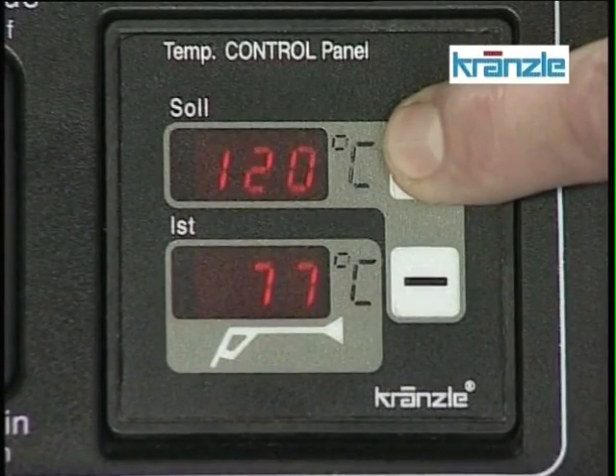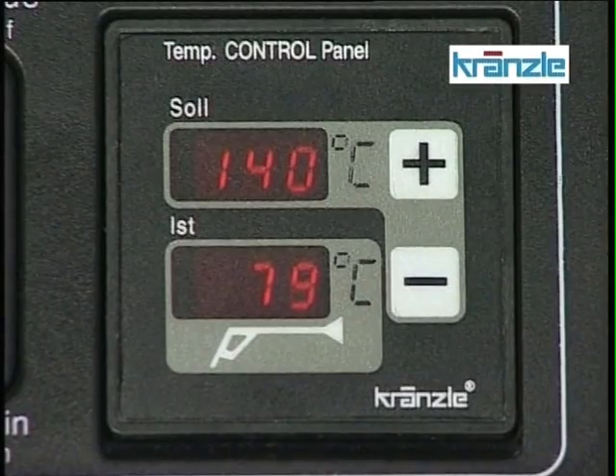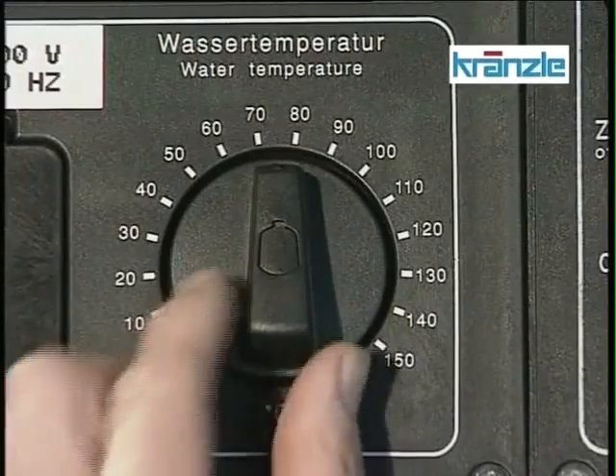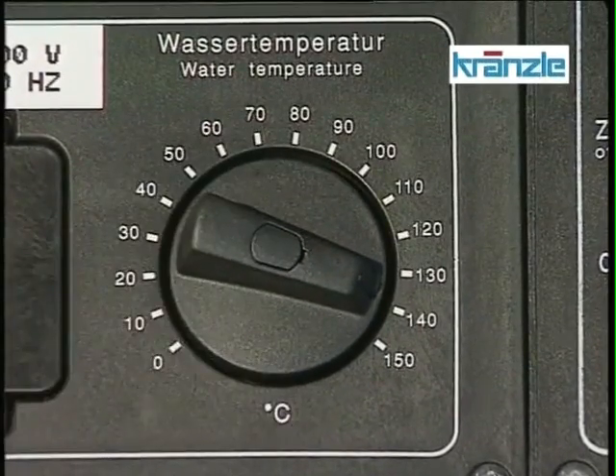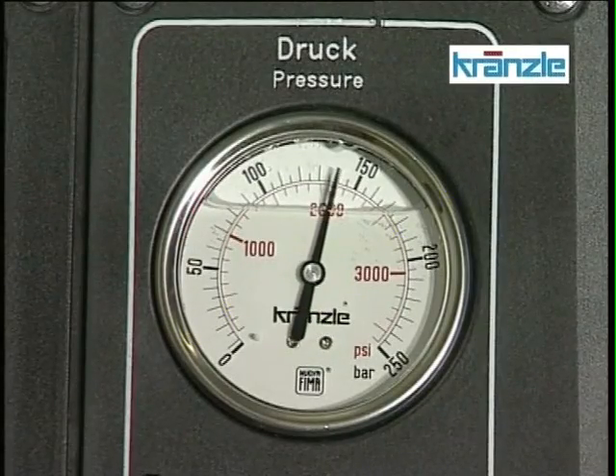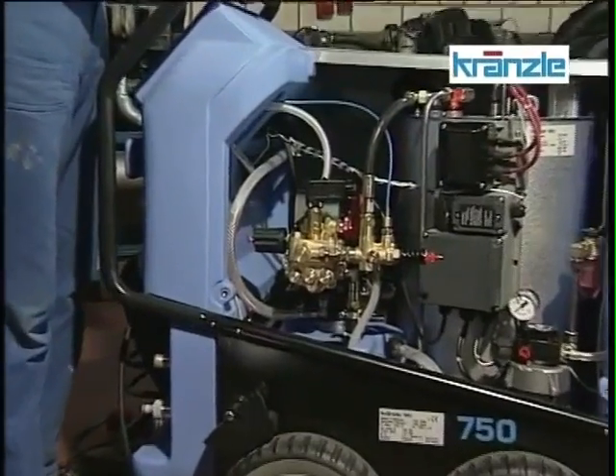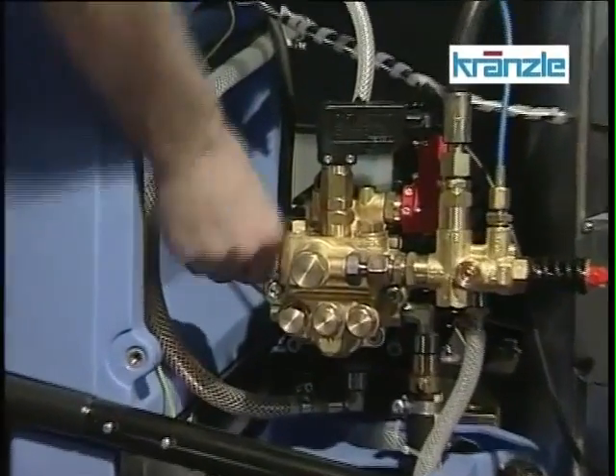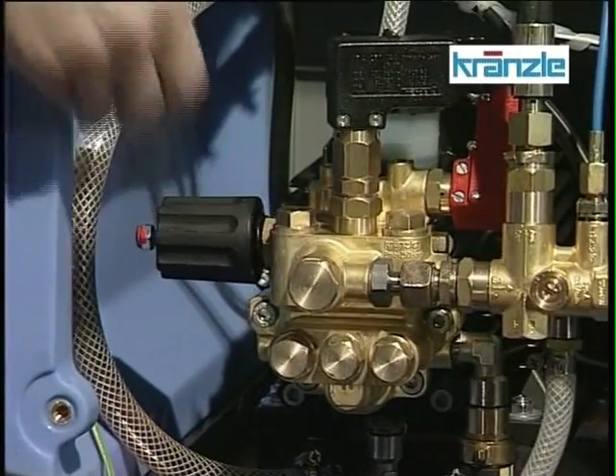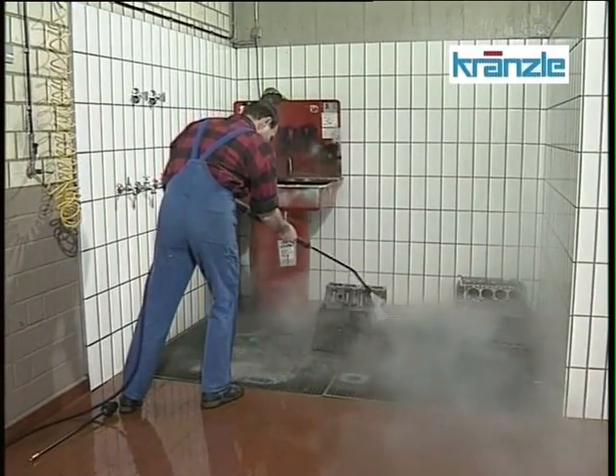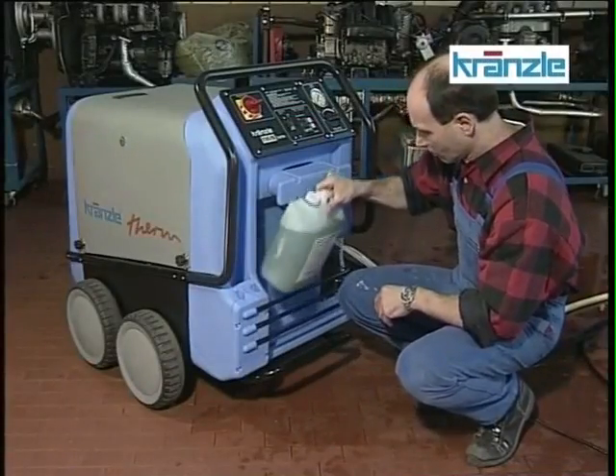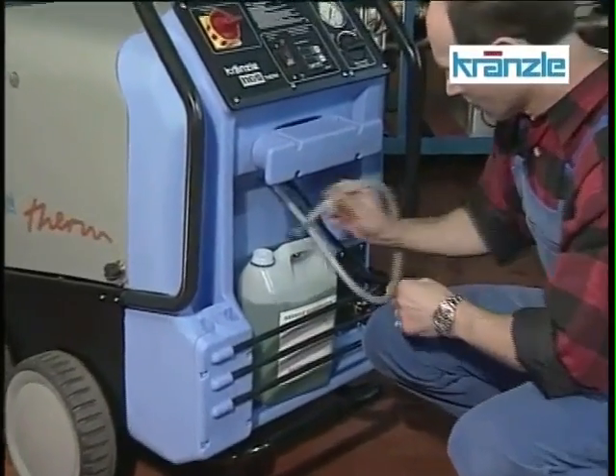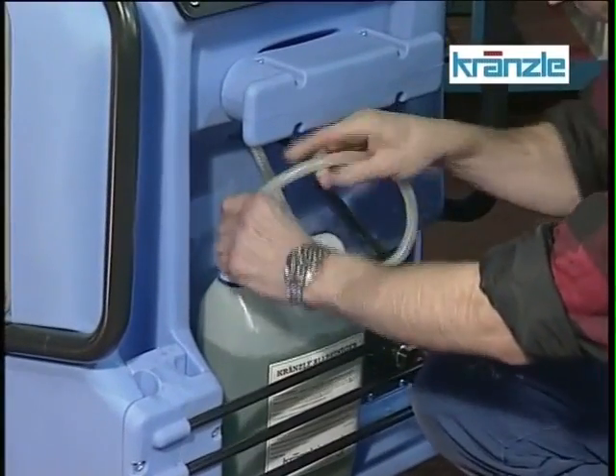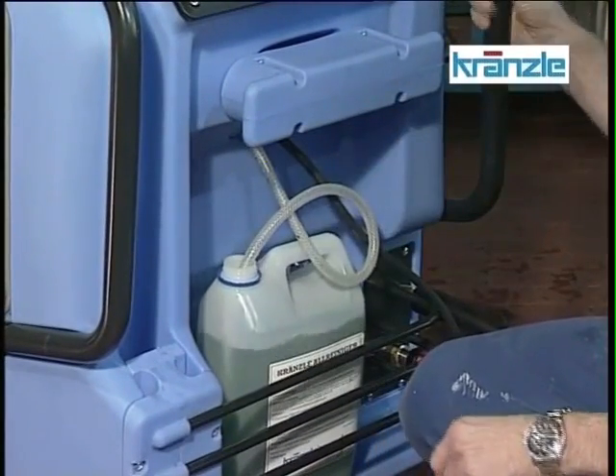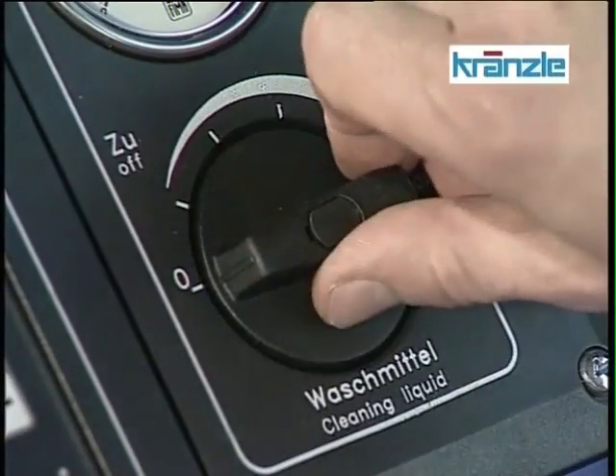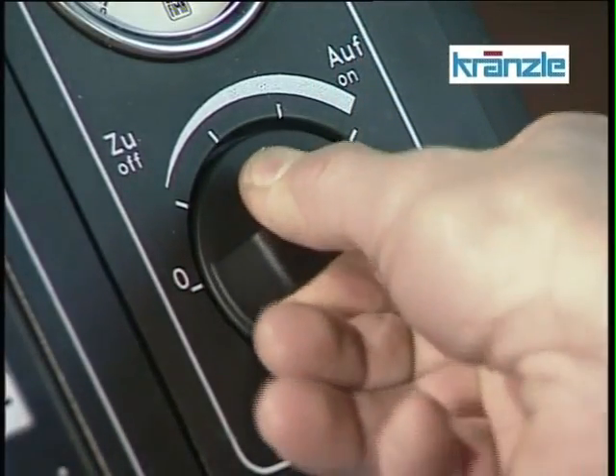This is how to activate the steam stage up to 150 degrees Celsius, and again at this knob on the 0 series. On all models, the working pressure and the steam stage are set on this hand wheel. If you're working with additional media, you will need to put this small hose in the container of medium. Now open the valve for the medium so that it can be sucked in by the pump.